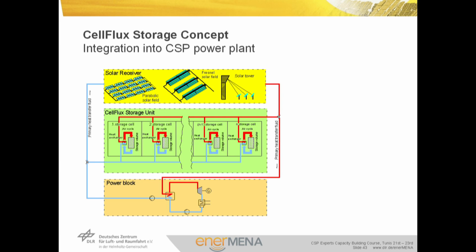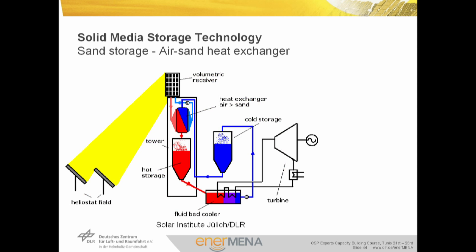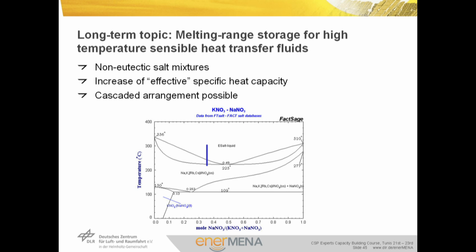This picture shows the integration of the Cell Flux Storage Concept into a CSP plant, where a storage unit is composed of various storage modules operated in parallel. Another solid media storage concept under development uses sand as storage material, with energy transferred to the working fluid by heat exchangers, similar to two-tank molten salt systems. Another concept under development uses non-eutectic salt mixtures as storage material, where the phase transition takes place over a wider temperature range, resulting in higher effective specific heat capacity.